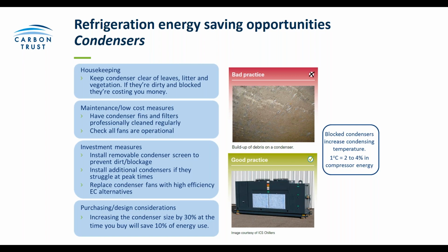If you're looking to invest in your condenser system, then it's likely to be accumulating dirt, so consider fitting a removable condenser screen. So this is essentially something that can just be hosed down or replaced when it gets dirty, and stops the condenser accumulating that dirt. And if your condenser is struggling at peak times, consider fitting an extra one to take the load off, essentially, that condenser.